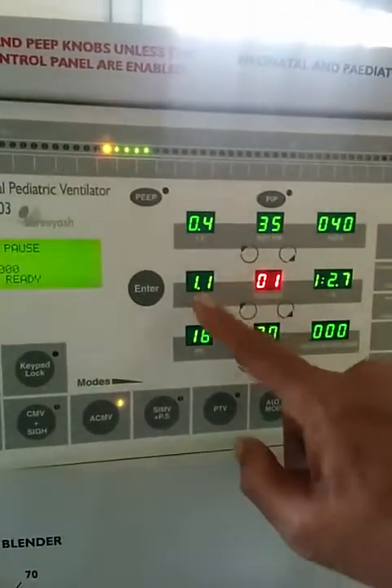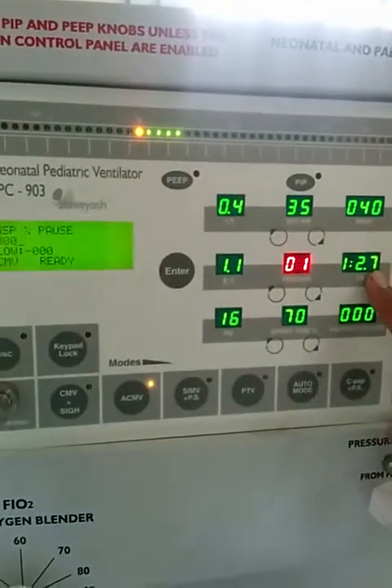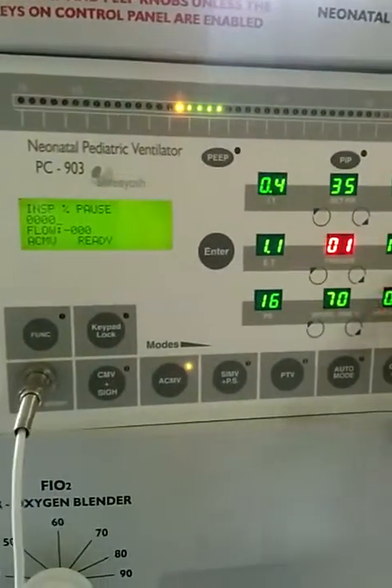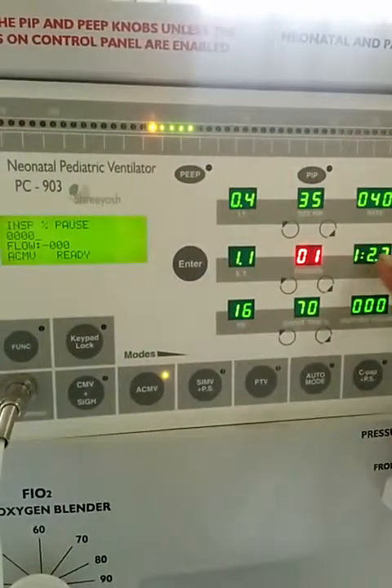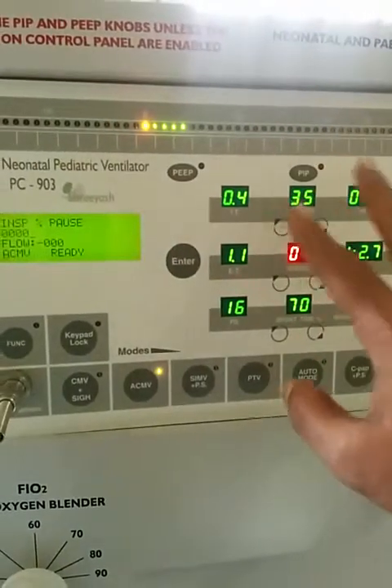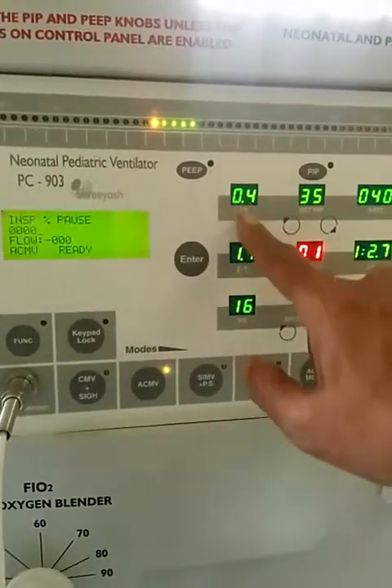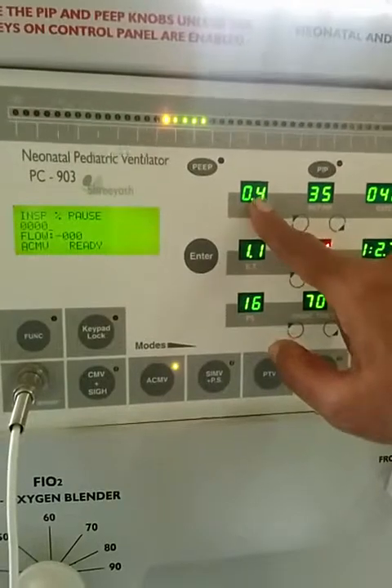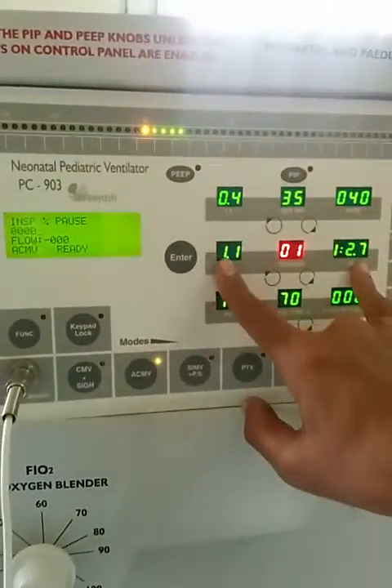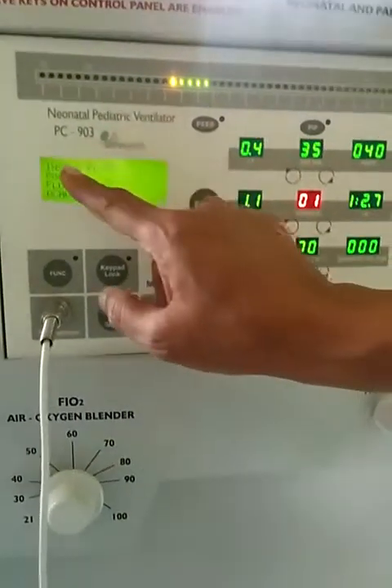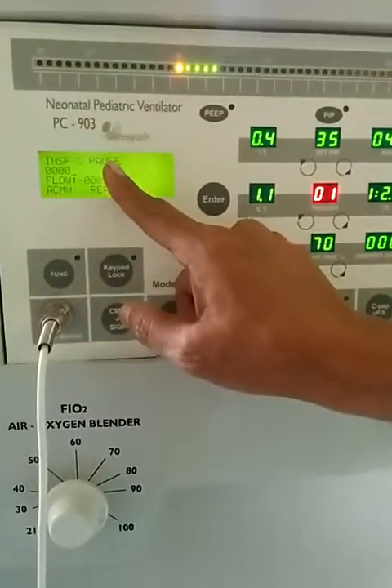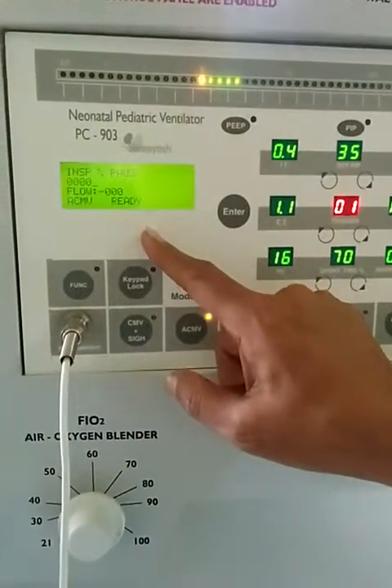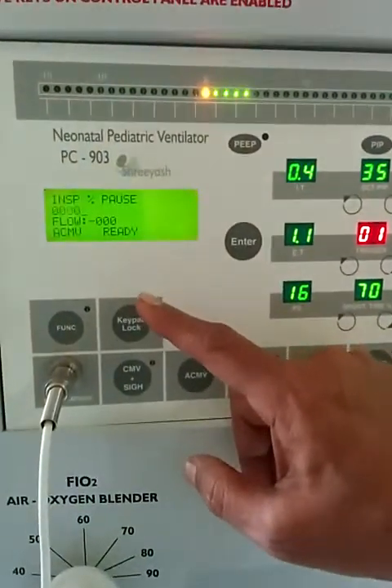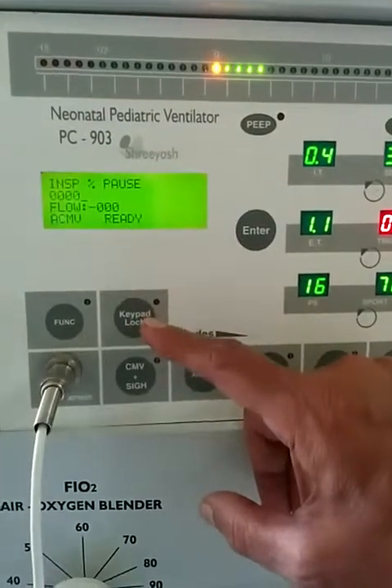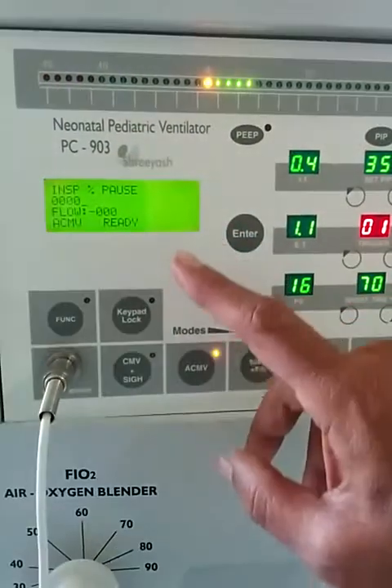So automatically the expiration time and the I:E ratio are set. You don't need to set the expiration time as well as the I:E ratio. The I:E ratio and expiration time depend on the setting of the inspiration time and the rate, and these are the byproducts of these two things. After which the display will ask whether you wish to set an inspiratory pause to enhance the oxygenation of the baby. But nowadays it's rarely used, so we will not set it.